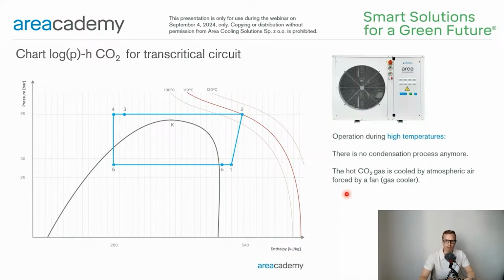The situation changes when the ambient temperature is high. In such ambient conditions, there is no condensation process, because the pressure in the gas cooler is higher than the critical one, and CO2 is in a supercritical state. The hot CO2 gas is cooled by the air forced by a fan of the gas cooler. At the outlet of the gas cooler, the CO2 pressure is reduced by an electronic expansion valve, called the high pressure valve, to the pressure in the liquid receiver. Finally, the liquid CO2 refrigerant flows out of the unit and supplies the evaporator expansion valve.